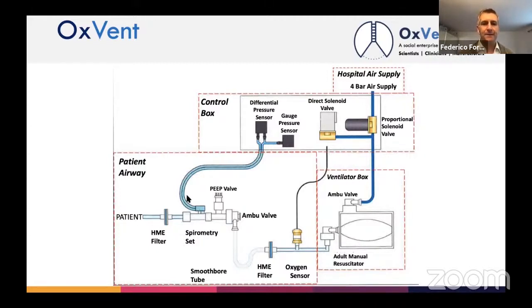And then there's a couple of filters, one here by the ventilator, one by the patient, for obvious reasons. And then in the system, there's a PEEP valve to retain some of the pressure in the lung of the patient when the patient breathes out. And there's a control box at the top, which sets the timing of the breathing: how many breaths per minute are delivered, how large each breath is, how long it takes to breathe in compared with breathing out, and so forth.